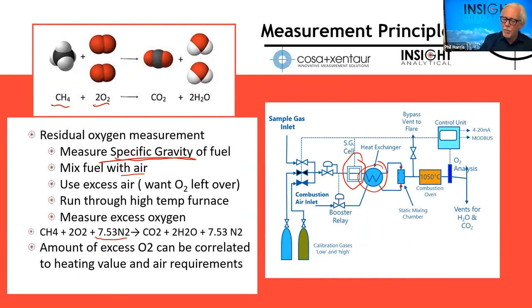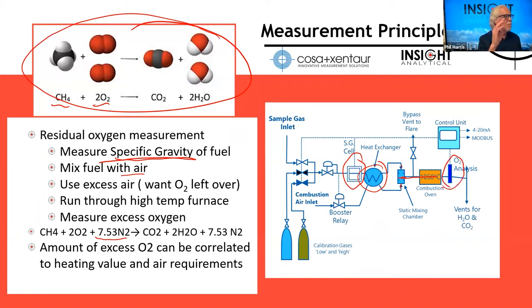So we do that by getting a really good mixture of the fuel and the air, heating it up, making this chemical reaction happen, and then measuring how much excess oxygen there is. So we put in a bit more oxygen than what we're going to need, and we see how much is left over at the end. We'll see as we go through this how the amount of excess oxygen becomes related to how much air I need. If I know how much I put in and I know how much was excess, it allows me to figure out exactly the right amount I should be putting in at the actual burner. So the amount of excess oxygen we measure can be correlated to the heating values and the air requirements of this burner to make it run the best.